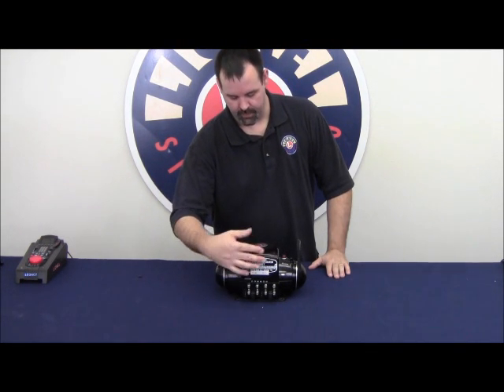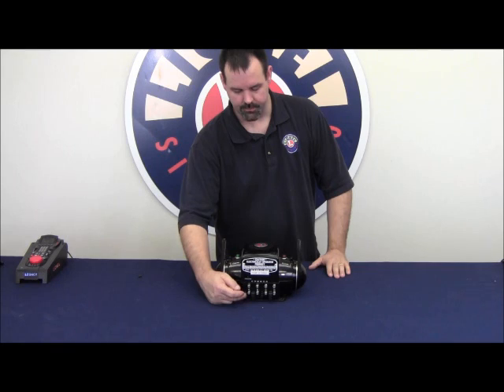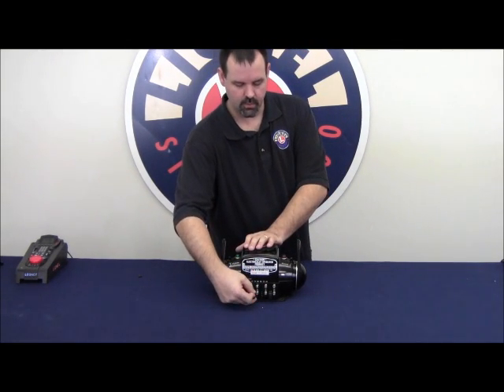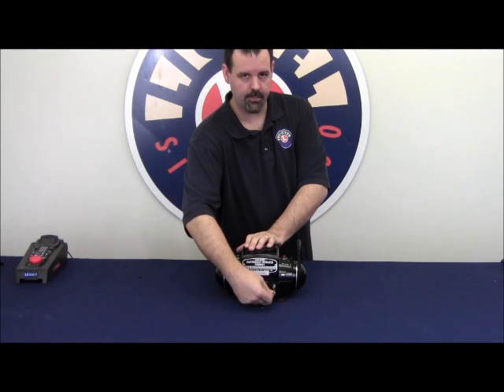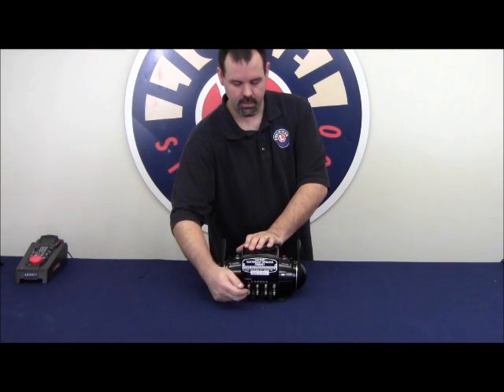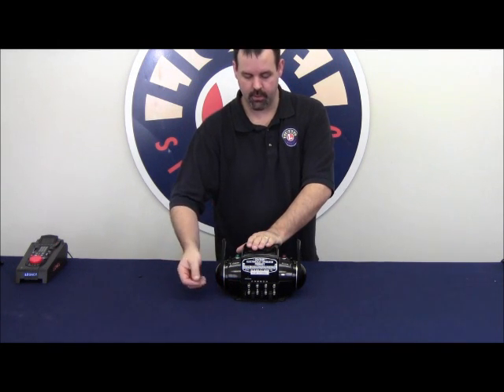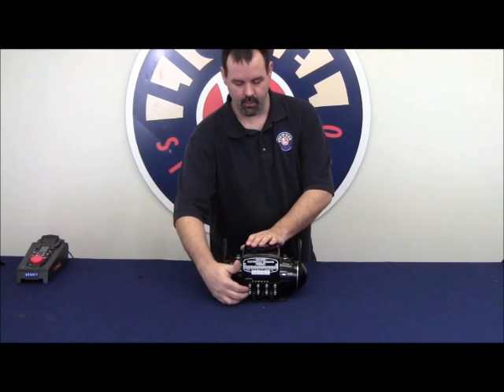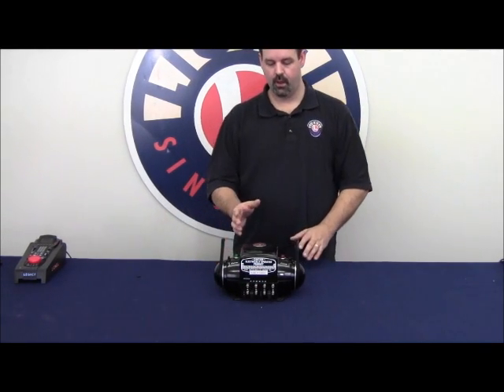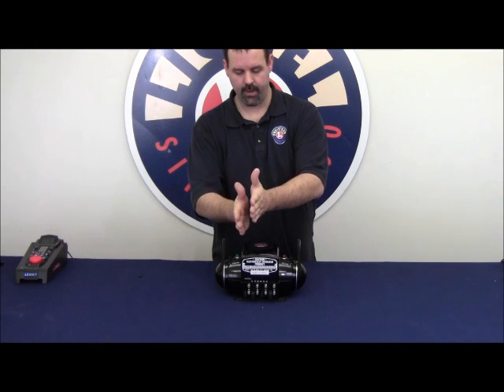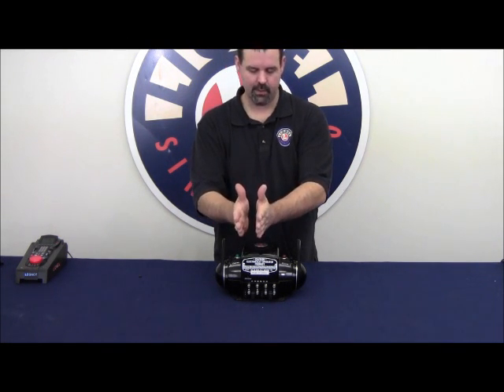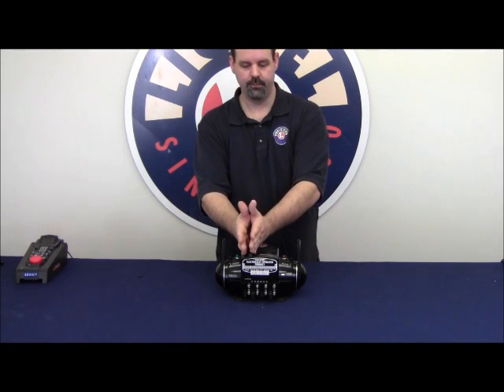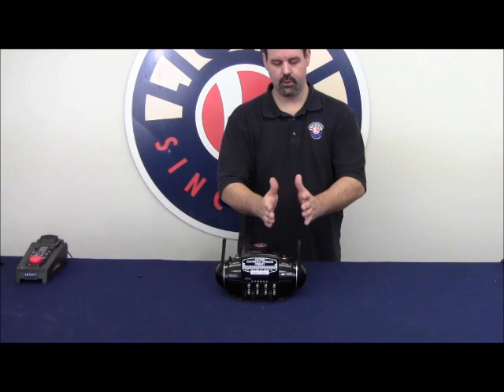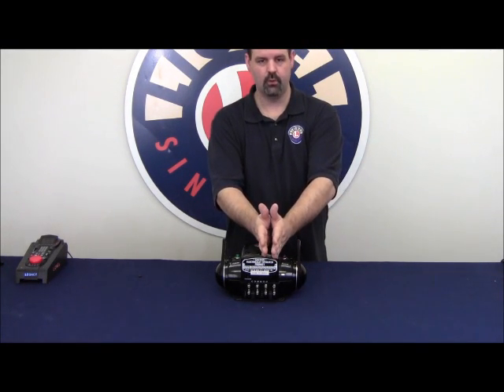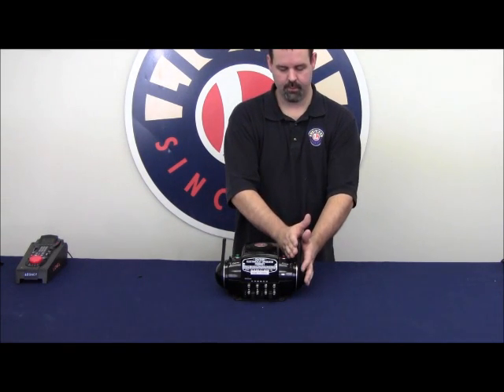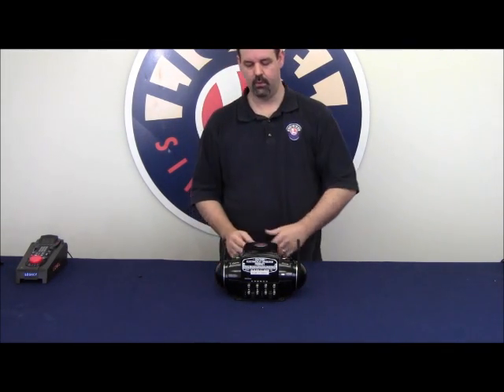On the front of the ZW housing, you have these Molex plugs. Out of the box, it comes with two jumpers, a jumper in the B position and a jumper in the D position. The open plugs is where the plug from the powerhouse that came with the transformer plugs in. So the 135 watt would plug in here and here, effectively giving you 7.5 amps divided equally, or I should say load balanced, over A and U and B and U. The other 135 watt powerhouse would give you 7.5 amps over C and U and D and U together. So you had 7.5 amps per these two channels, 7.5 amps per these two.